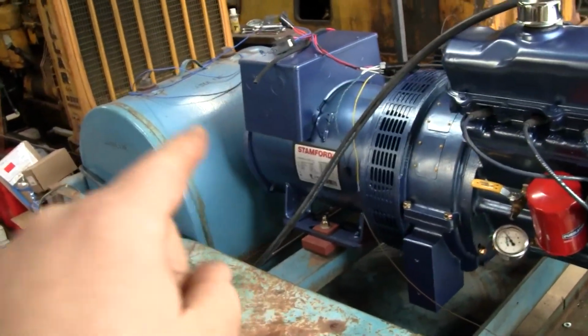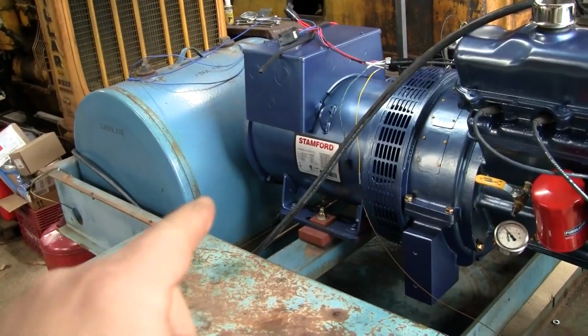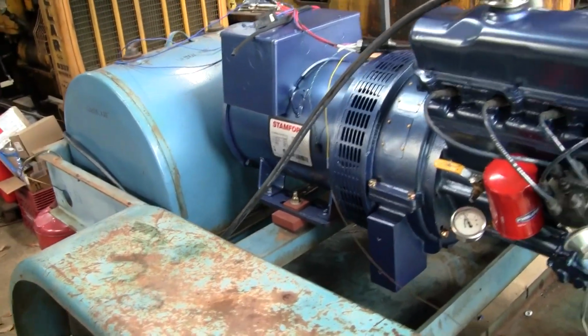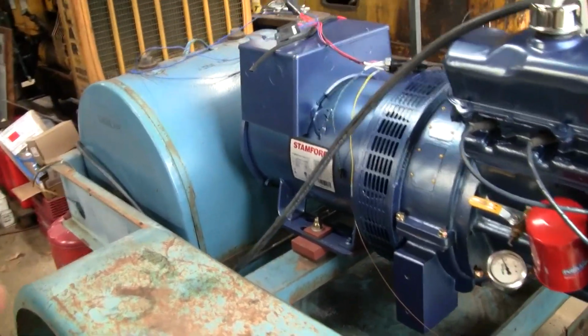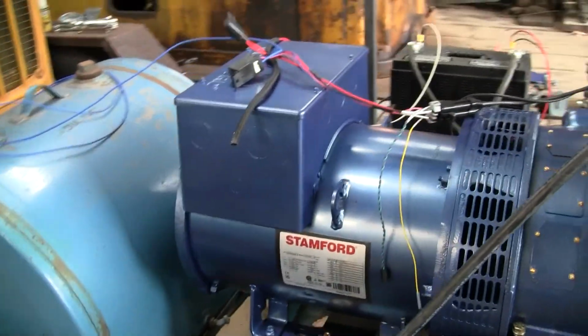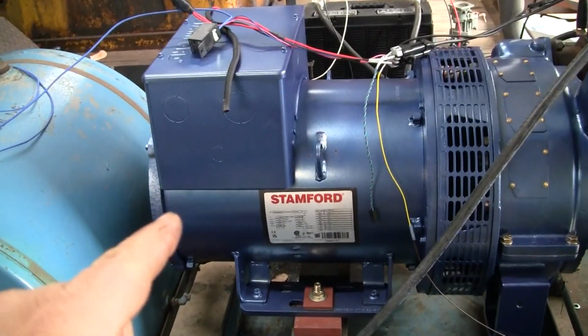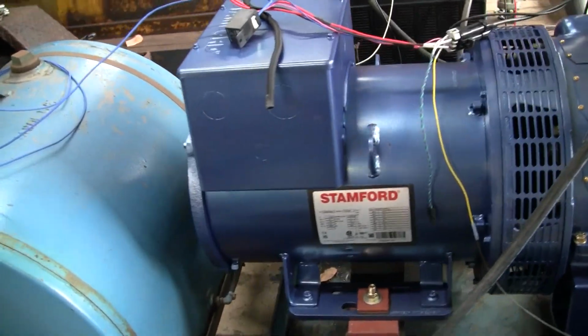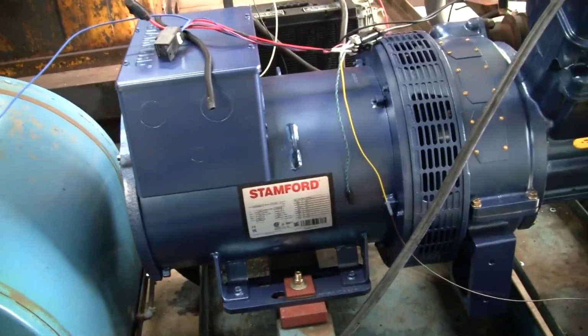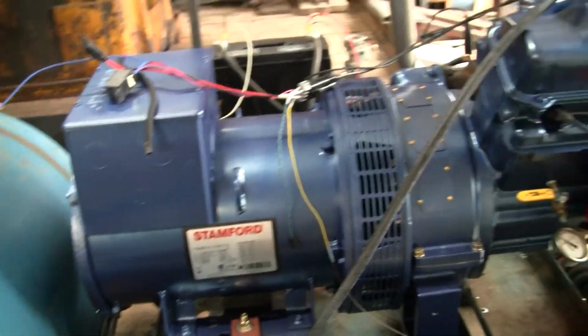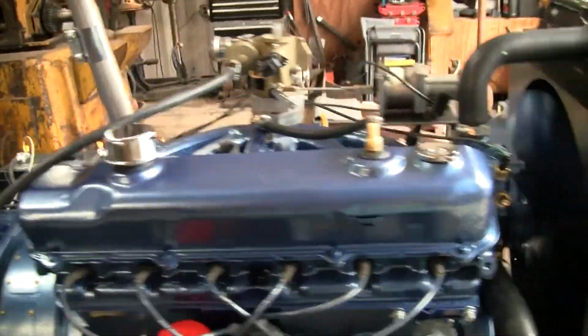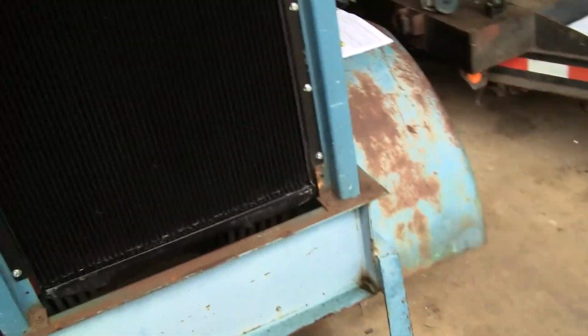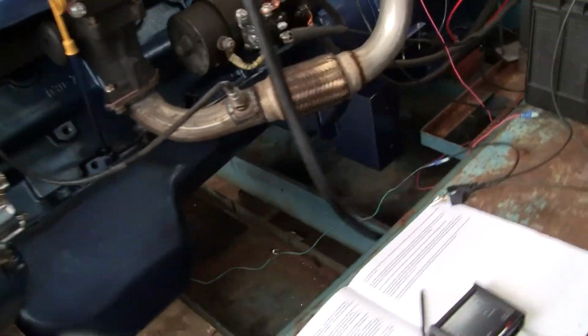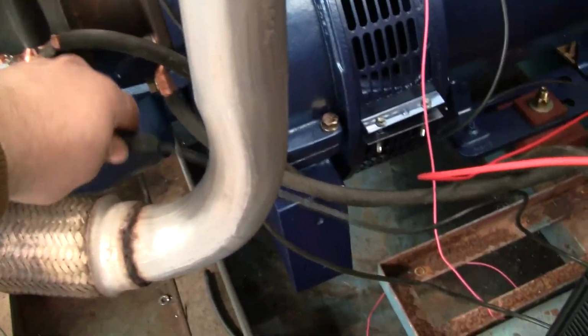I should also mention I've got the voltage regulator disconnected on the generator, so the only voltage the generator's making is residual. You don't want to idle a generator like this, or any generator with an automatic regulator, without first disabling the regulator. I better make sure this wire isn't getting burned on the exhaust.